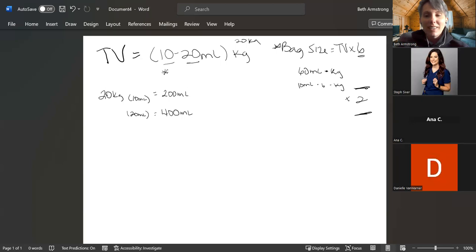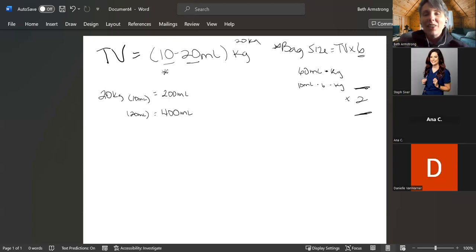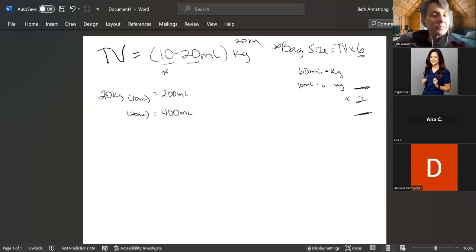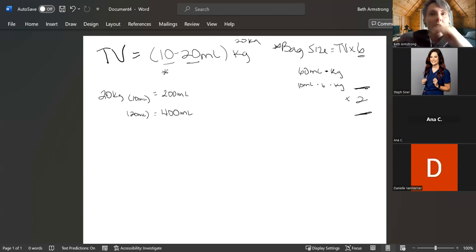Has anyone ever set up a ventilator? We have — for cataract surgeries. So you're probably fairly used to this — that's part of the starting process of knowing how to do tidal volume. And from there you have to know, looking at your manometer: what do we not want our pressure manometer to go above? 20 centimeters of water.